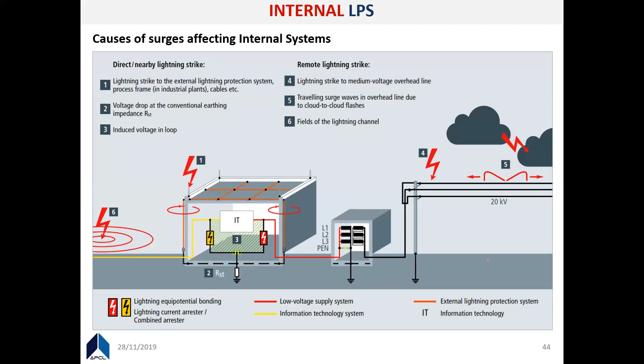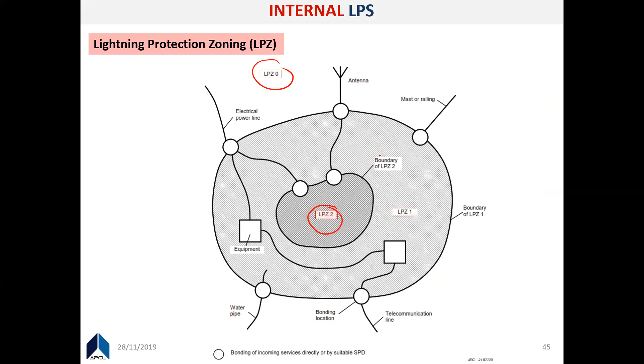And the lightning protection zoning is also important. The most exterior one is lightning protection zone 0. Likewise, when you go internally into the building, you go up to lightning protection zone 2, right? When you classify further, you have 0A, 0B, likewise, according to the boundary of the zone. Yeah, so the requirements for surge protection device selection are also given in what we discussed, BS 7671, 18th edition. All the parameters are given there. So correct connection is really important. Having an SPD is not the thing; you have to connect it correctly.